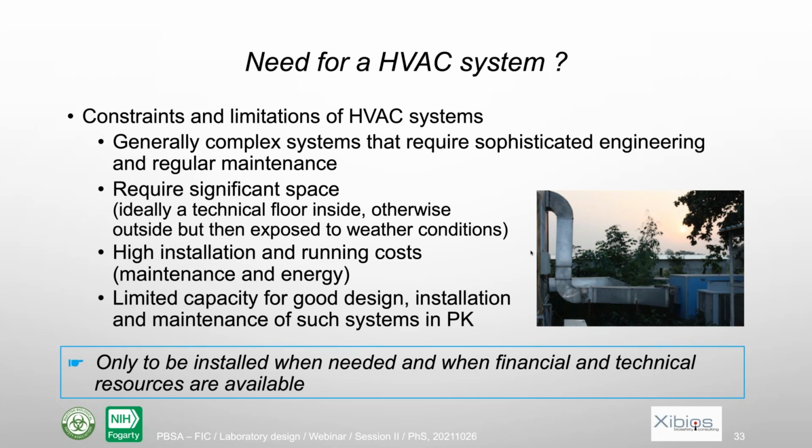Also, in this case, I think it's also a good story. This system here is on the top of a BSL-3 lab for TB work, liquid culture of tuberculosis. And actually, from the start, that system never worked properly. It was noisy, it was not maintaining the right temperature and so on. And so the people in the lab were not happy with that. And they also did not trust the system because it could not be fixed. And so the lab manager decided, we don't use it anymore.